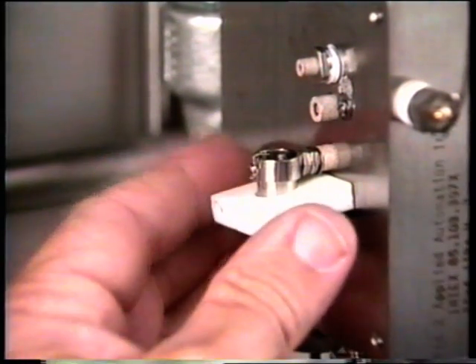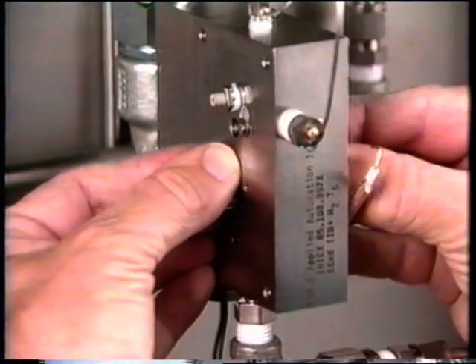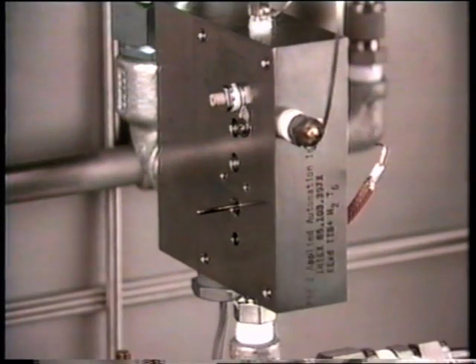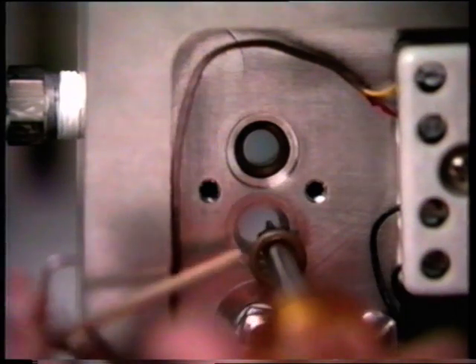Remove the baffle plate from the detector body. Pull out the collector electrode assembly. Push the bias ignite and collector insulators through the detector body and lift them away. Be certain the insulator O-rings come out with the insulators. Place new insulator O-rings in the O-ring cavities in the block. You may need to work the rings into place with a blunt tool.